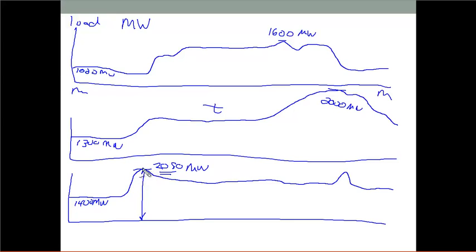So everybody starts their heat in the morning. They've all got electric heat, and because they wake up and they're cold, my peak is in the morning, and then it kind of tapers off because it gets warmer, and then maybe right before they go to bed, they go, oh man, it's cold, and they turn it back on for a little while. So your load profiles change over the course of the year, right? And the profile, of course, where the peak occurs changes over the course of the year. This is a winter peak here in Florida. This is a summer peak here in Florida when everybody's running their AC versus their heat.